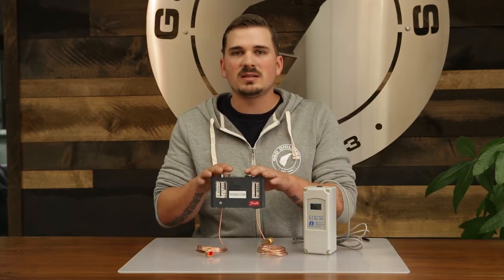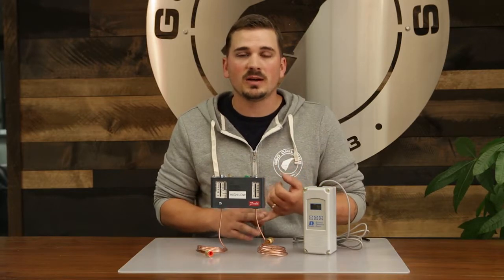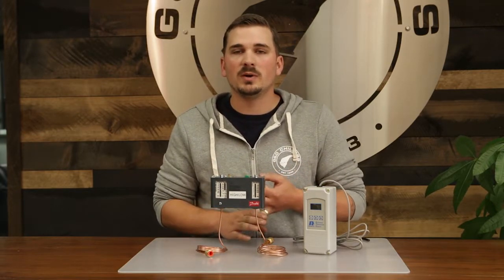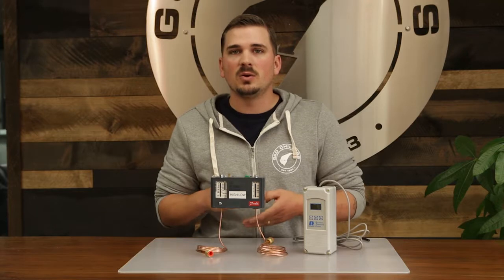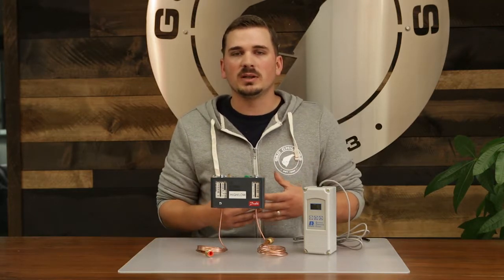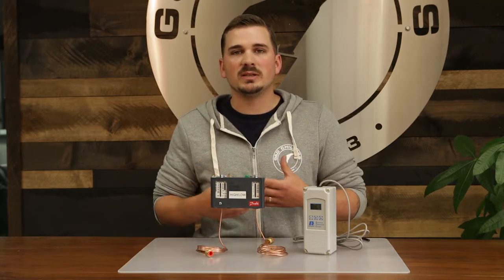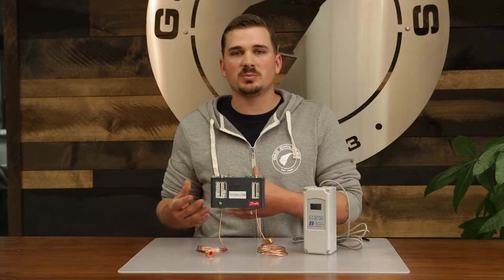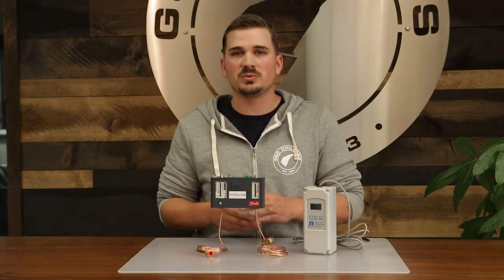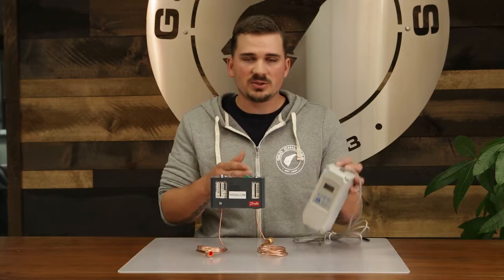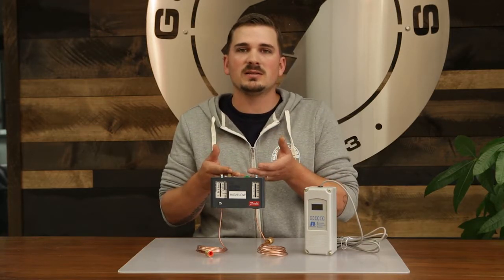If for some reason this thing trips due to a bad fan motor, we're not getting enough airflow, hot weather coming in, a blocked condenser, or hitting it with an extremely high load will cause the glycol temperature to increase dramatically, which can increase the pressures on the system when the refrigerant passes through. What happens then is you still got a process pump that's running, you're still sending glycol out, but the compressors can't run because this is tripped.